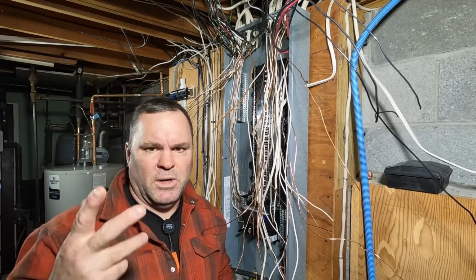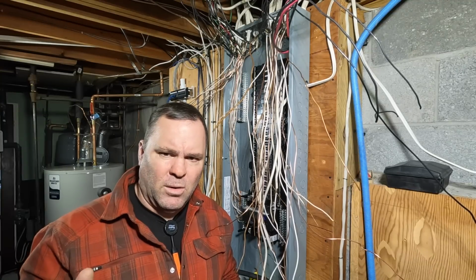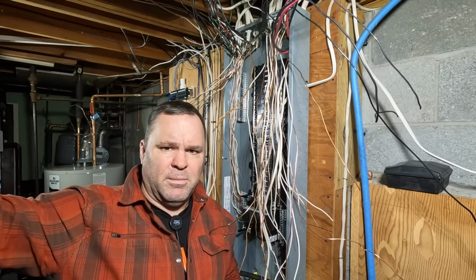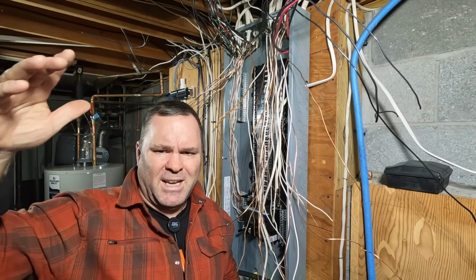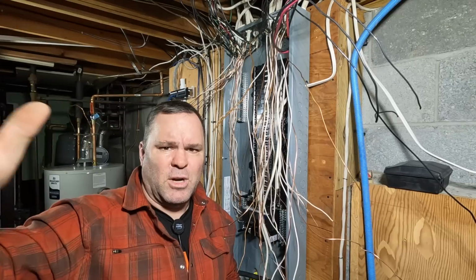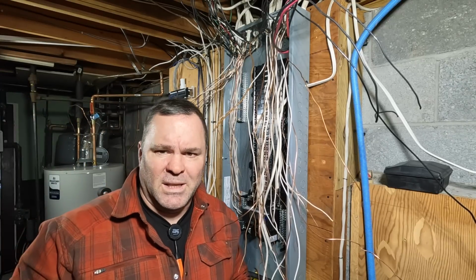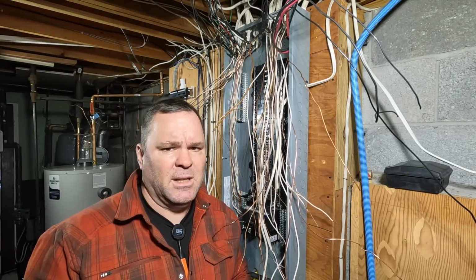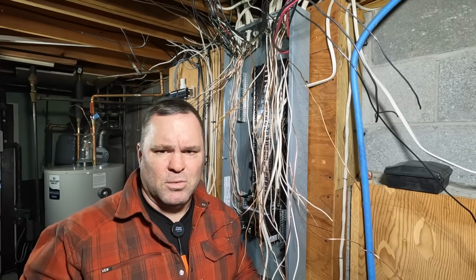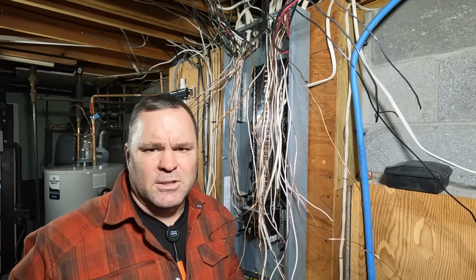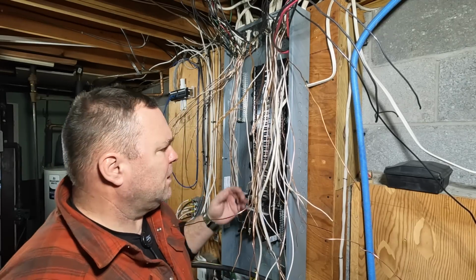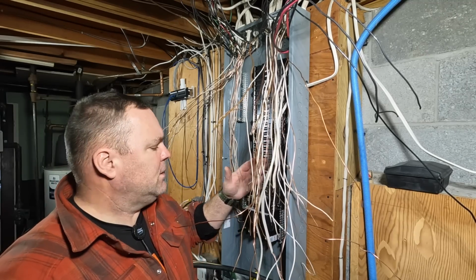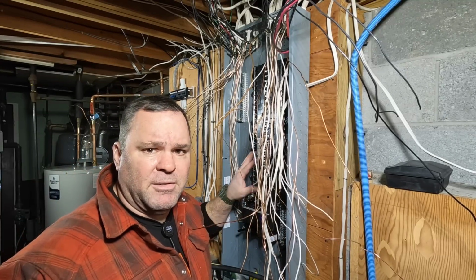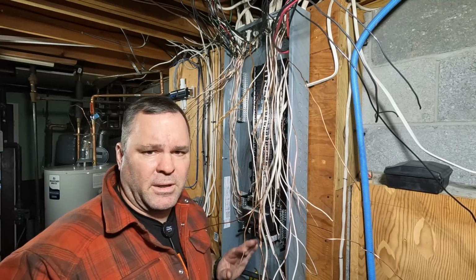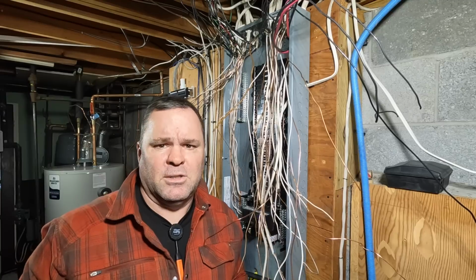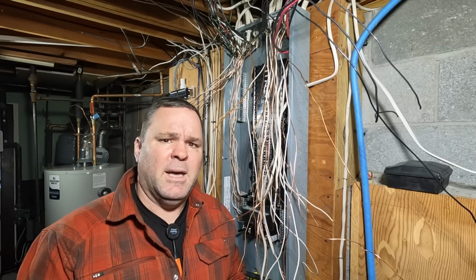And it's going to serve 2 purposes. One, to clear a ground fault, okay? And then also, if you have a line surge from your utility company or a higher voltage comes in contact with the service drop that comes into your house, okay? Also, when lightning strikes, lightning can induce a voltage onto the line without even touching the line. Just the magnetic field around that lightning strike can induce a voltage on the circuit that's coming into your house, your service drop. And so we want to make sure that if that lightning wants to get to ground, we give it a connection to ground through our grounding electrodes, which is the main water pipe here and the 2 ground rods.